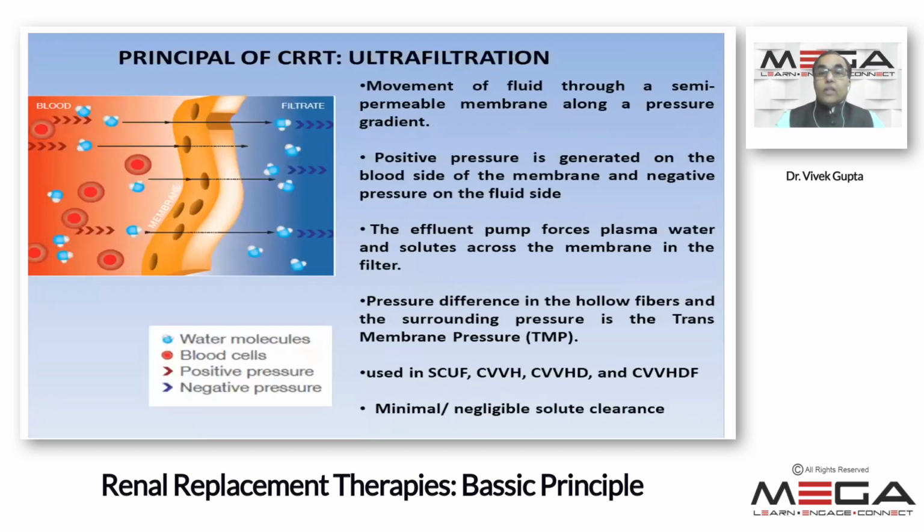Then third is ultrafiltration, which means removal of fluid. Because there is a positive pressure generated on the blood side, a good amount of fluid can be taken out with the help of a fluid pump.